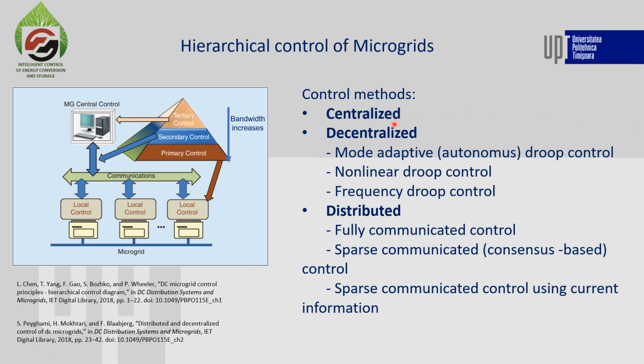The secondary control is mainly set in the microgrid central controller together with the tertiary control, which can be remotely located from the distributed generators, and thus communications are required. This control generates voltage shifting signals to the primary control level with the aim to eliminate the DC voltage deviation caused by the primary droop controls. Moreover, it's also possible to implement the secondary control level locally inside the distributed generators.